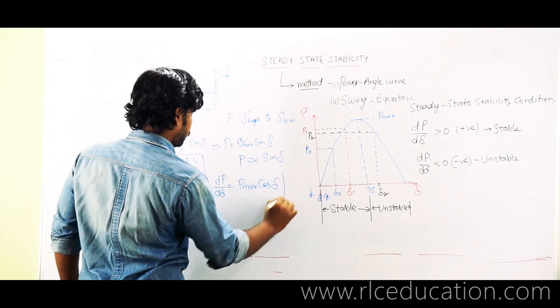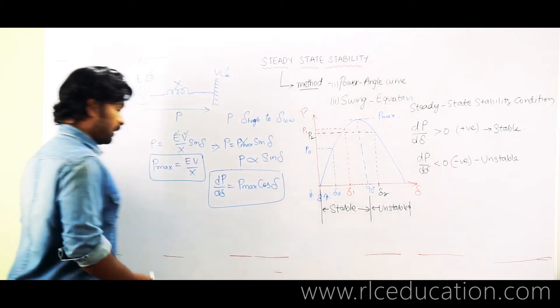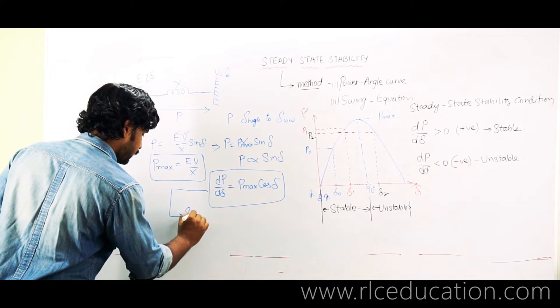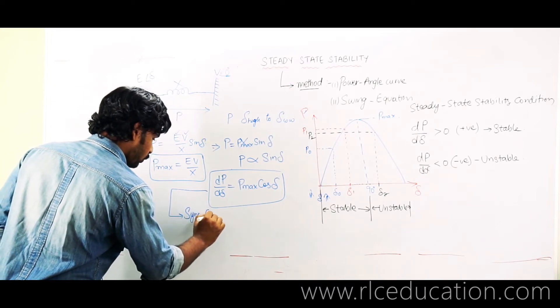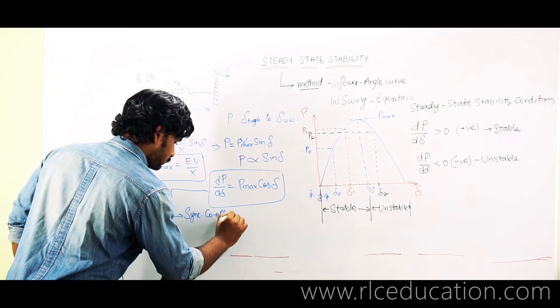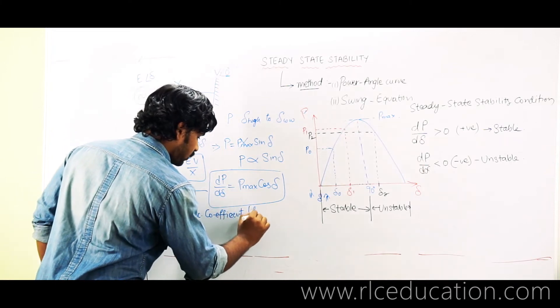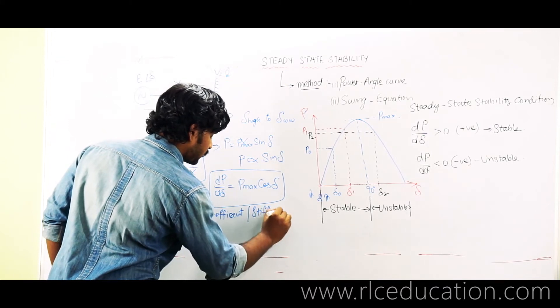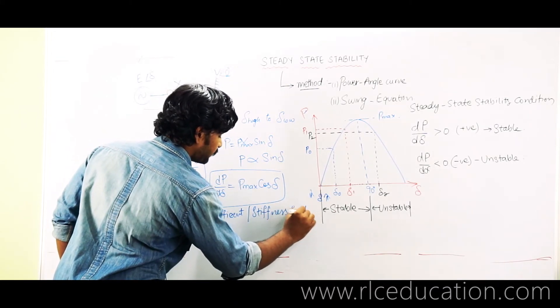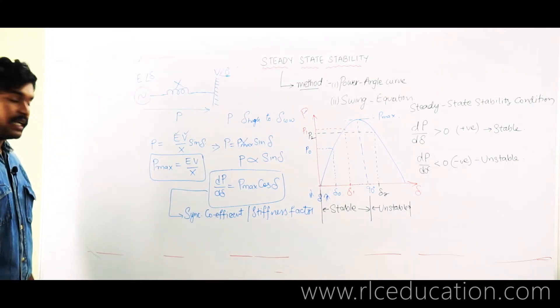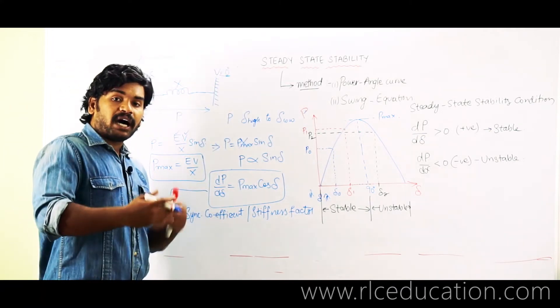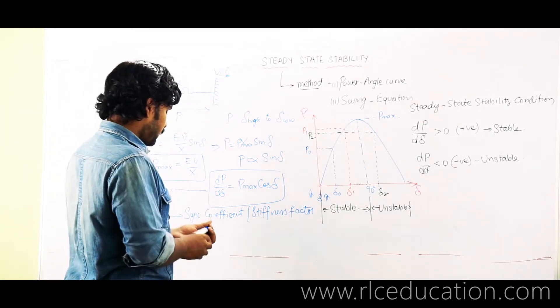This term Pmax·cos(δ) is called the synchronizing coefficient, also known as the stiffness factor of the generator. The stiffness factor indicates how much margin is available before the machine is driven into instability.